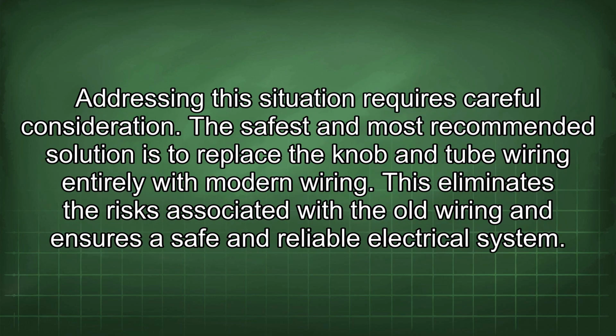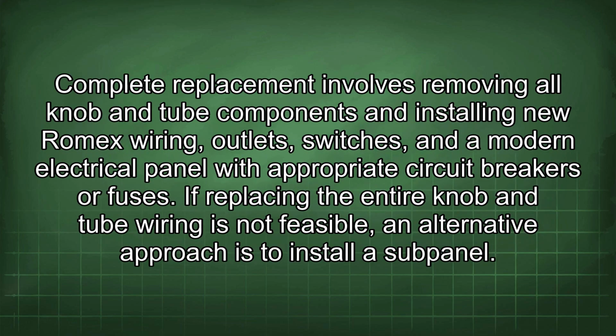Addressing this situation requires careful consideration. The safest and most recommended solution is to replace the knob and tube wiring entirely with modern wiring. This eliminates the risks associated with the old wiring and ensures a safe and reliable electrical system. Complete replacement involves removing all knob and tube components and installing new Romex wiring, outlets, switches, and a modern electrical panel with appropriate circuit breakers or fuses.